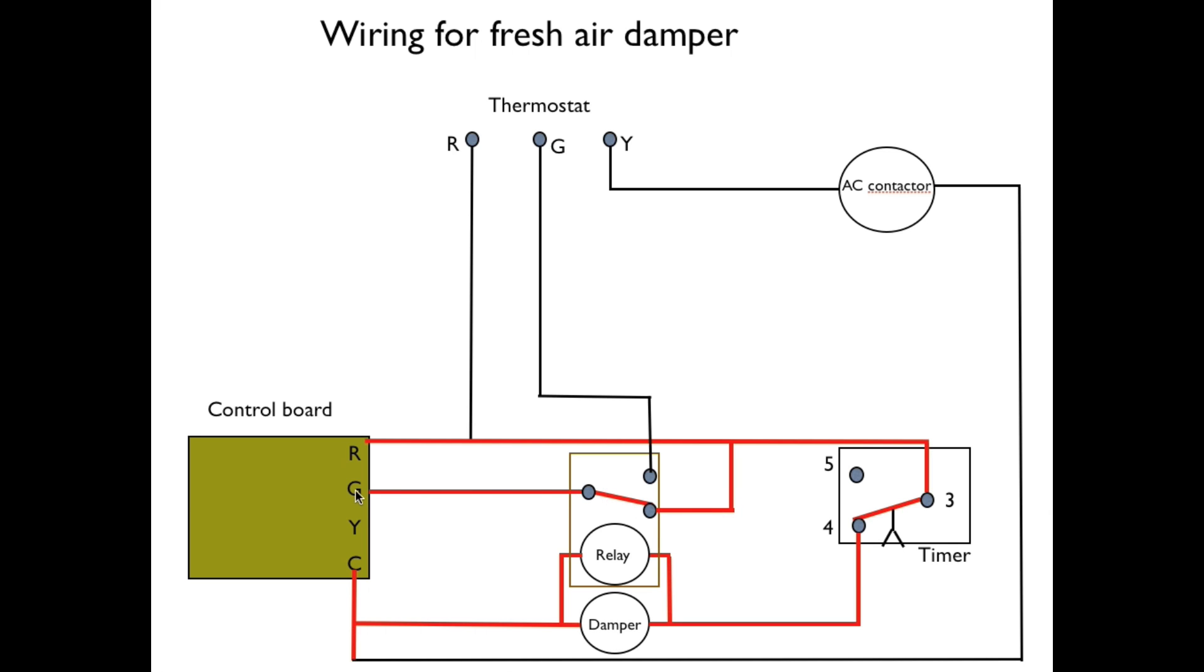What it will not do is allow any power up to G at the thermostat, which could backfeed and go through the air conditioning and energize the air conditioning contactor.